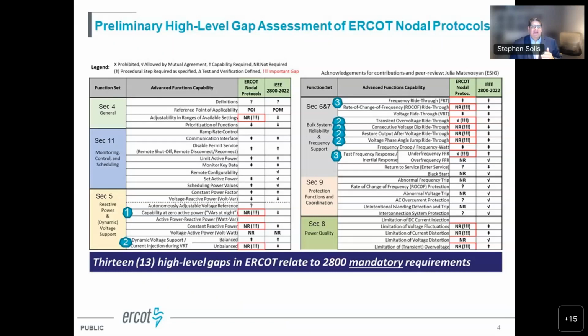And then you see item 2, all the 2s there are probably what's coming next, where we need to look at all of our ride-through requirements. We're taking the lessons learned from the Odessa events, all of those issues. We see a couple of opportunities for sure that while we have an overarching performance requirement that's good, we need to be more detailed so that the developers and those interconnecting to our system have crystal clear expectations of what they need to be able to ride through.